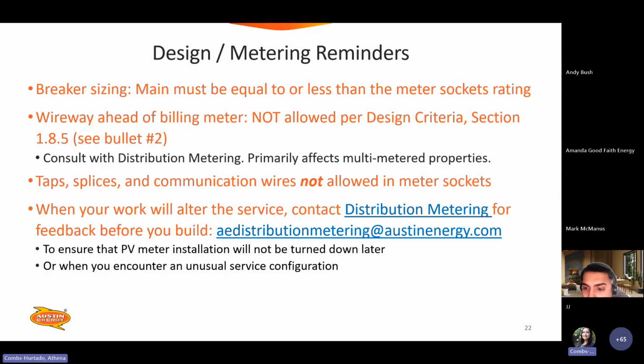All right, some metering design reminders. Breaker sizing: the main must be equal to or less than the meter socket rating. Wireway ahead of the billing meter is not allowed per our design criteria manual. Taps, splices, and communication wires are not allowed in the meter sockets.